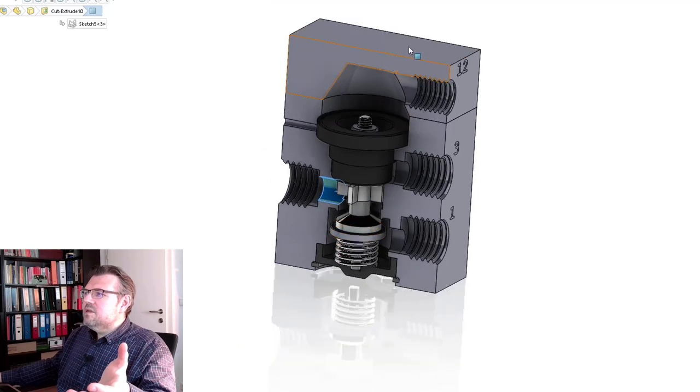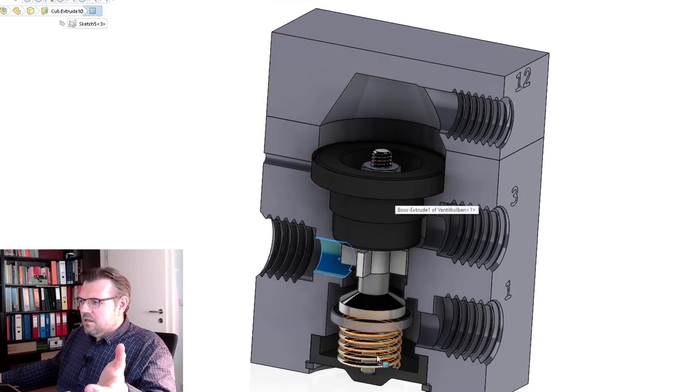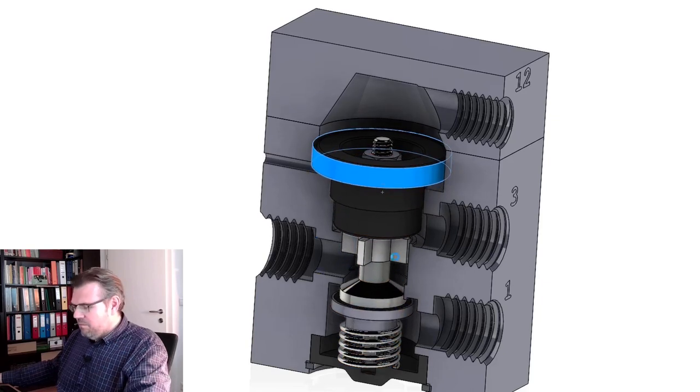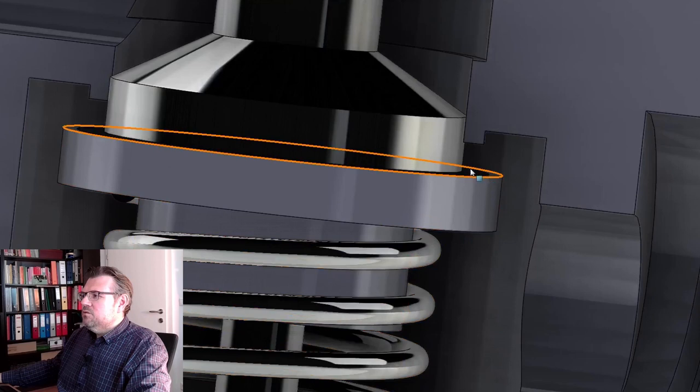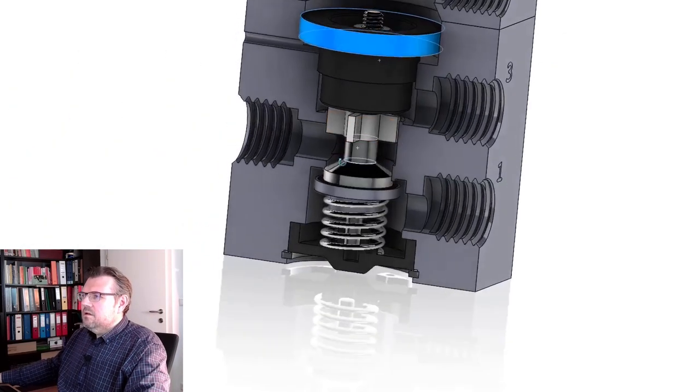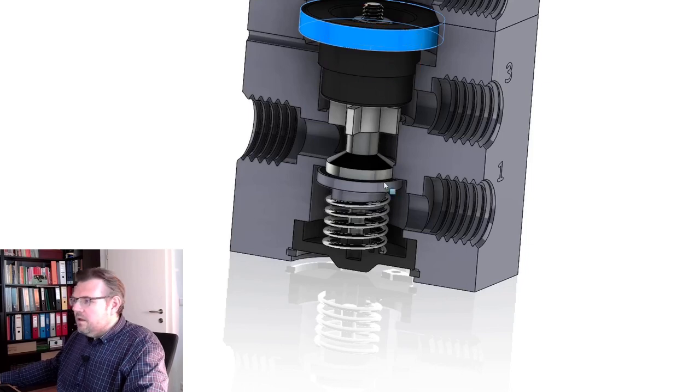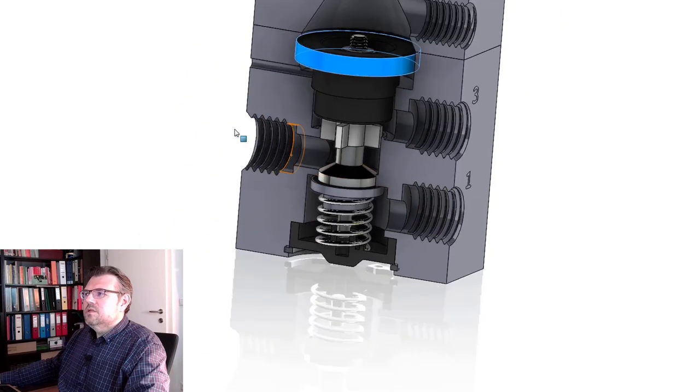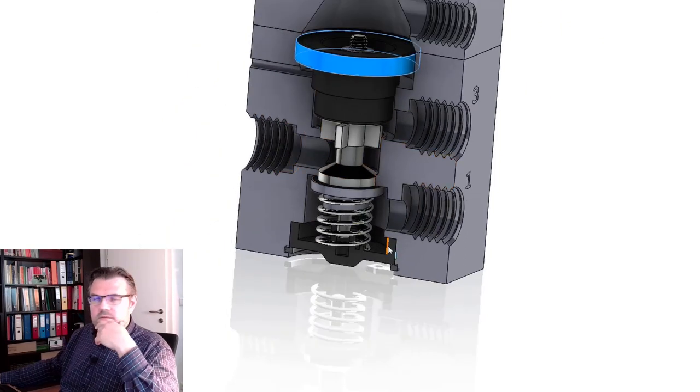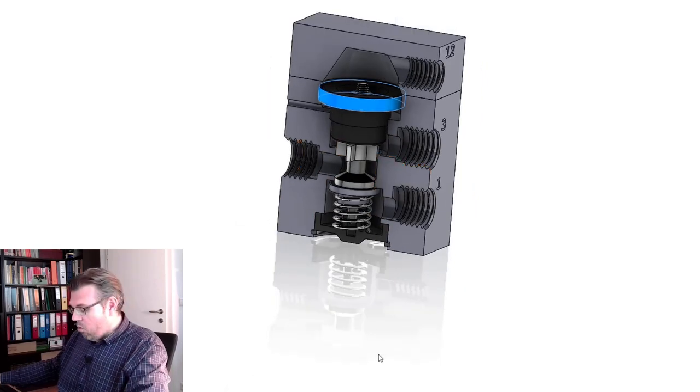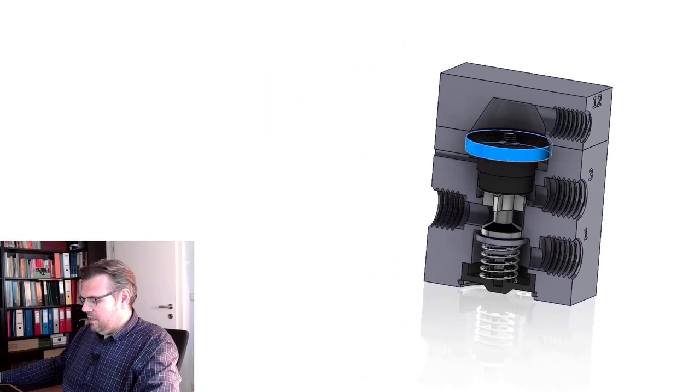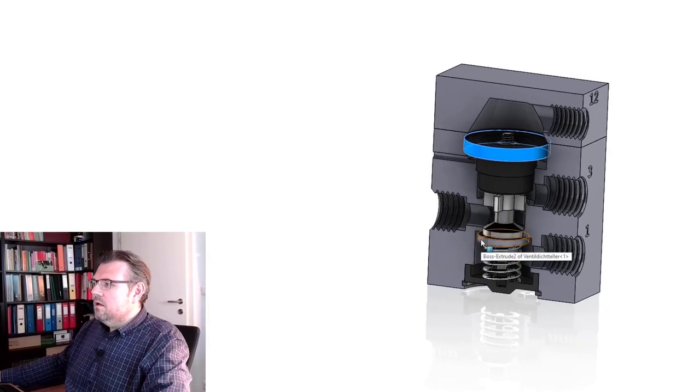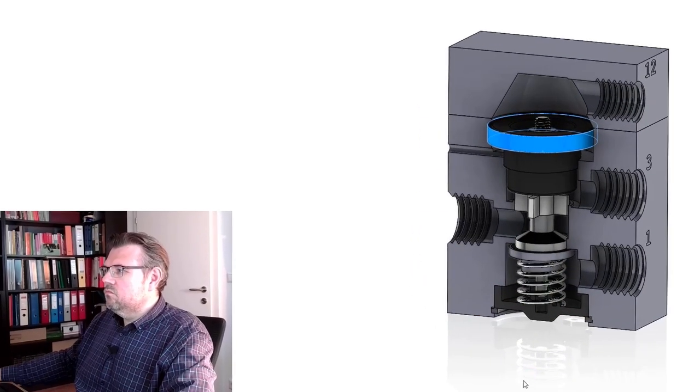Once we release the pressure here on the 12 side, the spring will unload, this will go up. Somewhere in the middle, we have again the situation where we connect all things to each other. And if it move in further, this will be pressed here and we are sealed. 1 and 2 is again sealed, and 2 and 3 is opened. So this is a pneumatically operated valve, this is a pneumatically operated valve, 3-2-way valve, and with overlapping.